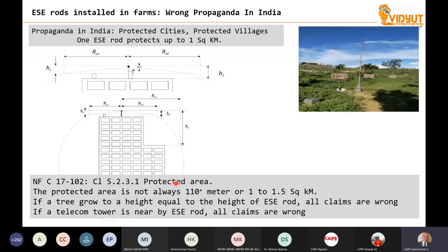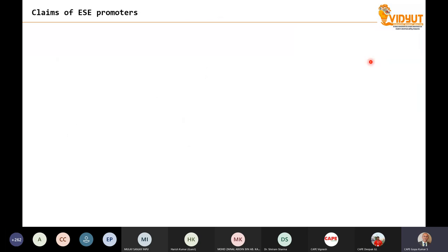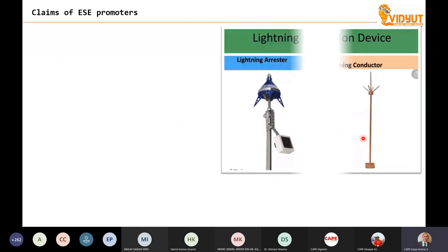So NFC, this particular clause, explains the protected area. The protected area is not always something plus or minus 110 meters. The proponents, the supporters, say each rod can protect up to 1.1 to 1.5 square kilometers. And you must understand that even in the documents of the ESE standard, these are not correct. Then again, what do the supporters say?